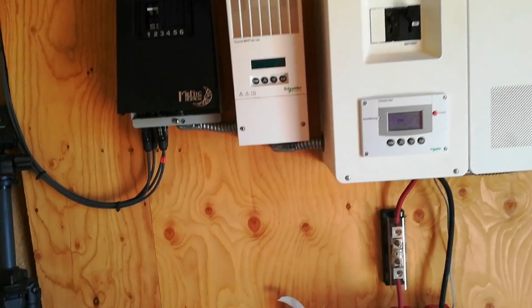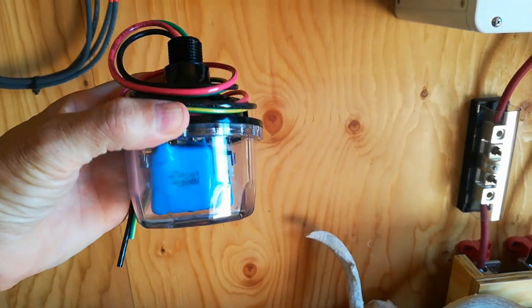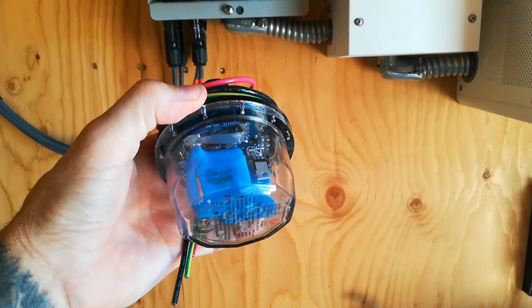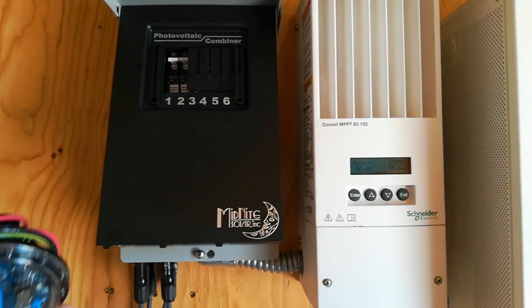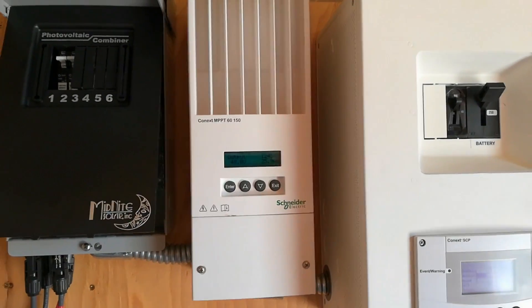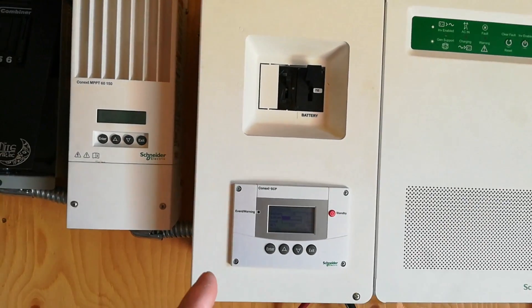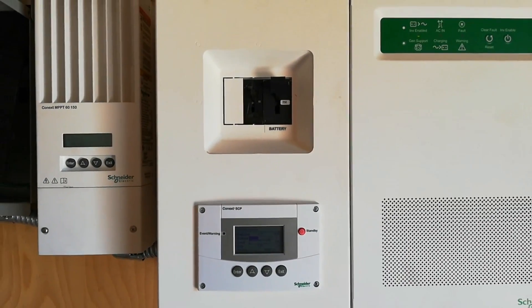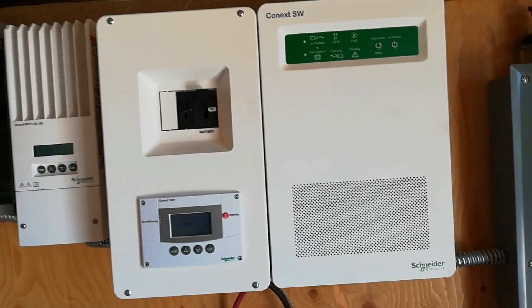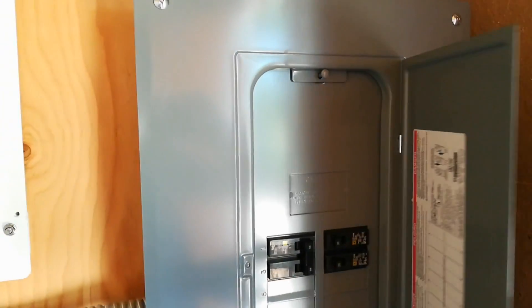I've purchased three surge protectors from MidNite Solar, and these are each designed to be installed in a specific location. The one I have in my hand is a 300 volt DC, and that's going to be installed in our combiner box to protect the load side of our charge controller. Then I have a 115 DC that will be installed on the DC side of our inverter, and a 300 AC to be installed on the AC side of the inverter, and that will actually be installed here in the breaker box.